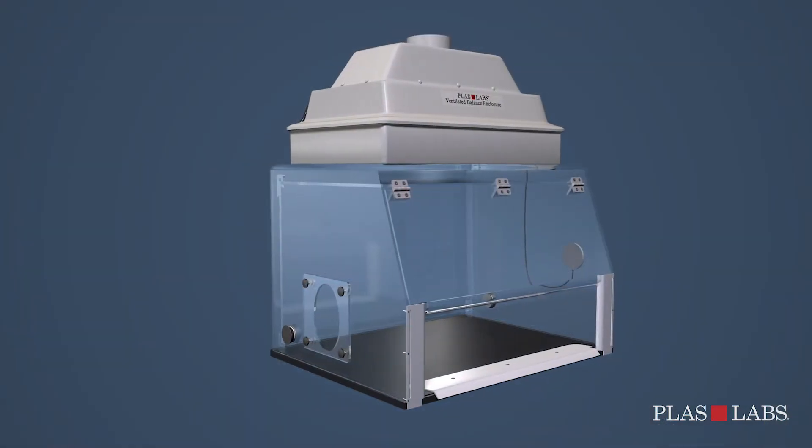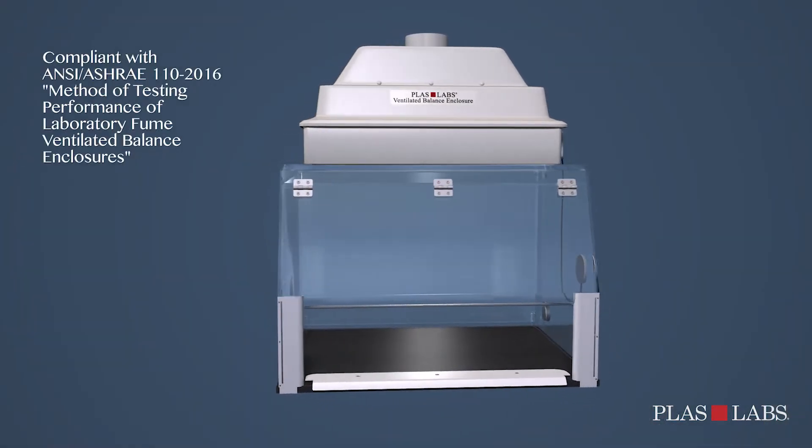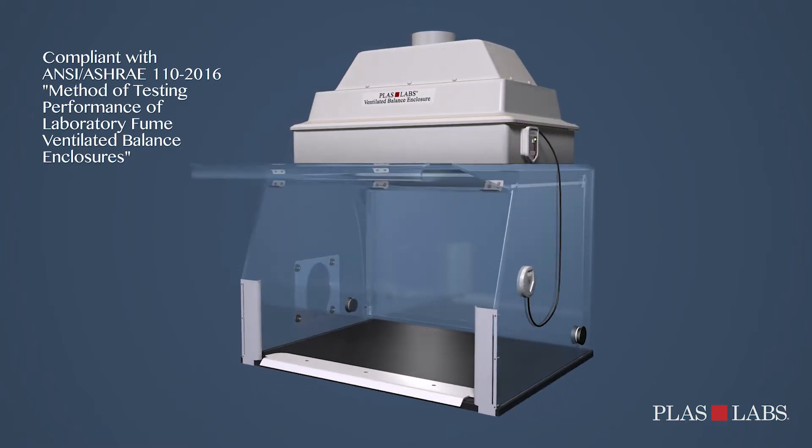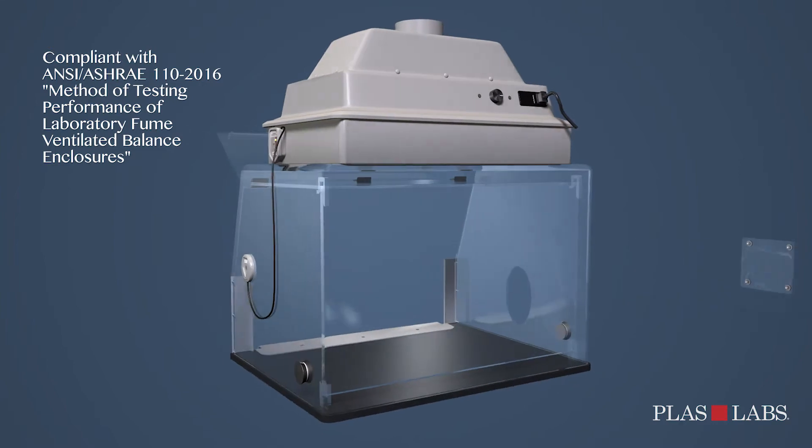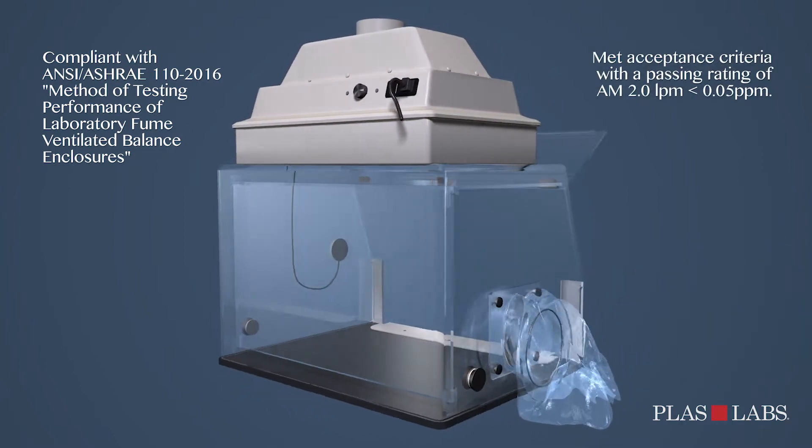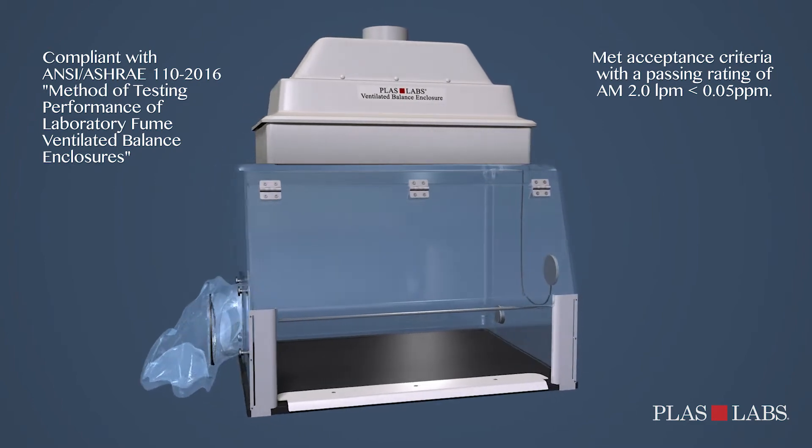The 900 VBE series is compliant in accordance with guidelines provided in the ANSI ASHRAE 110-2016 method of testing performance of laboratory fume ventilated balance enclosures, and has met the acceptance criteria with a passing rating of AM 2.0 LPM less than 0.05 PPM.